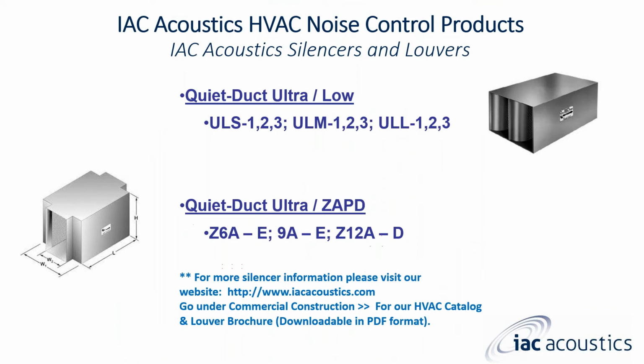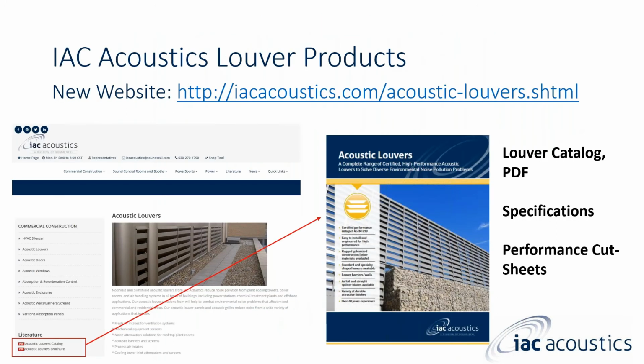We also then have our Quiet Duct Ultra Low Series silencers. These actually handle the 31.5 octave bands. And we still have it, and we're still pumping them out. Our Quiet Duct Ultra ZAPD, zero added pressure drop. You're going to see here that for W2 over here on the silencer, the 6, the 9, and the 12, that is the openings of the width only. You can stack these as high as your heart desires. But these are custom type silencers for those sizes of width only. So if you need help with these, contact me. I'd be glad to go over these with you.